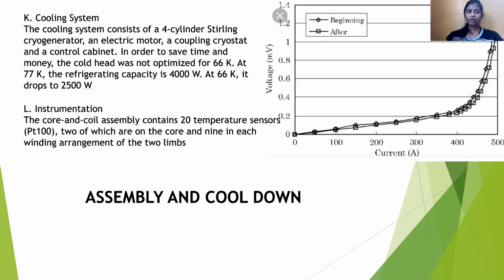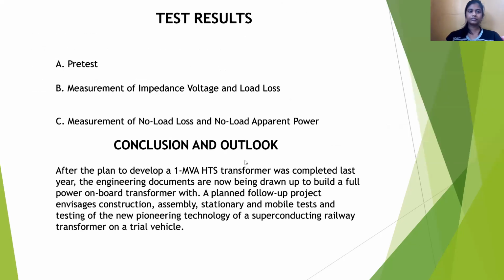Instrumentation. The core and coil assembly contains 20 temperature sensors, platinum 100, two of which are on the core and 9 in each winding arrangement of the two limbs. Assembly and cool down. Test results. Pre-test, measurement of impedance voltage and load loss, measurement of no load loss, and no load apparent power are the 3 points while doing the test.